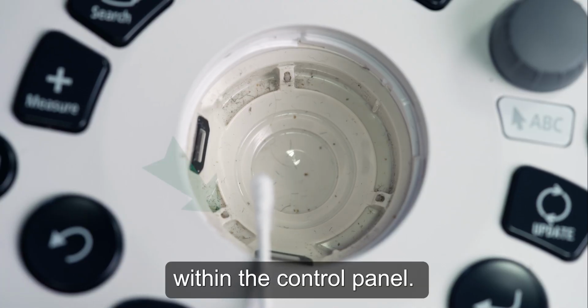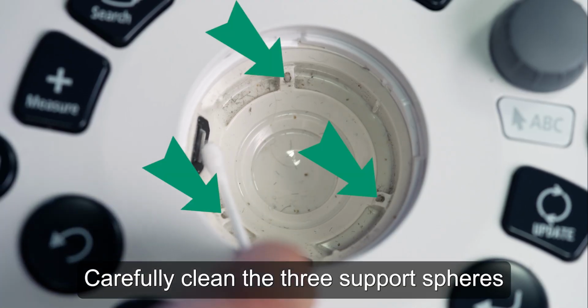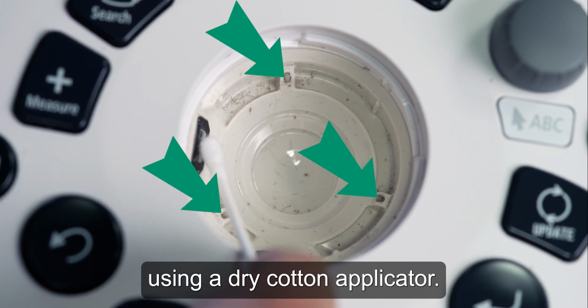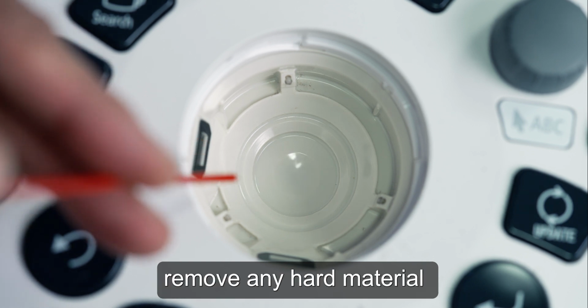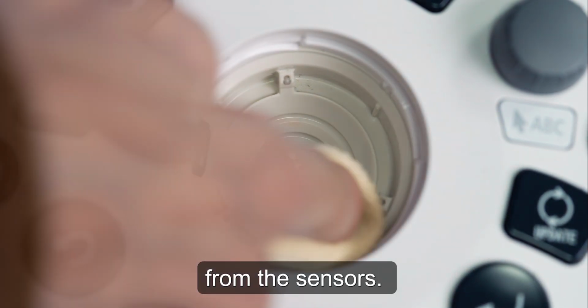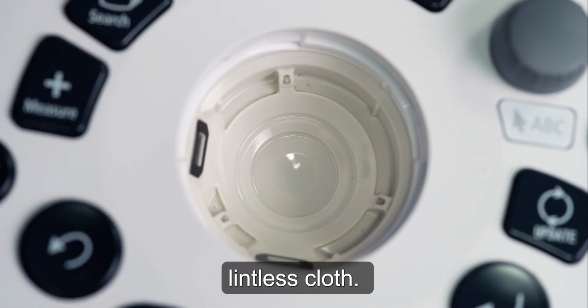Within the control panel, carefully clean the 3 support spheres and grooves using a dry cotton applicator. Use an air duster to remove any hard material from the sensors. Finish cleaning with a dust-free, lintless cloth.